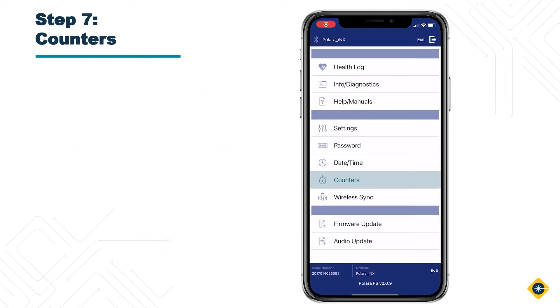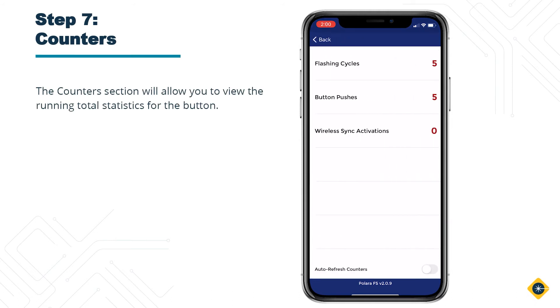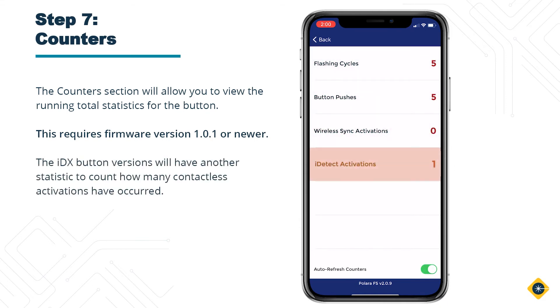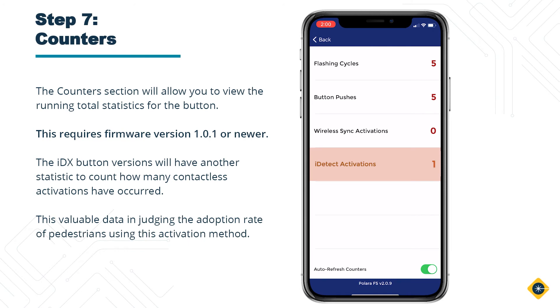Step 7: Counters. The Counters section will allow you to view the running total statistics for the button. This requires firmware version 1.0.1 or newer. The IDX button versions will have another statistic to count how many contactless activations have occurred. This is valuable data in judging the adoption rate of pedestrians using this activation method.